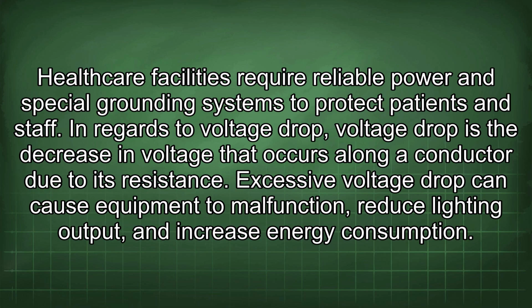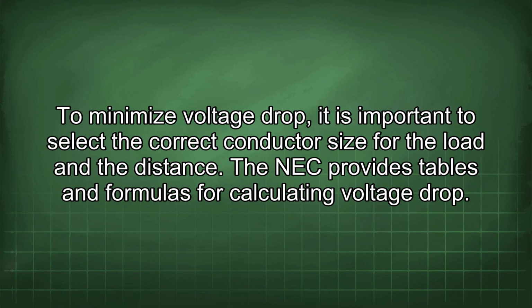In regards to voltage drop, it is the decrease in voltage that occurs along a conductor due to its resistance. Excessive voltage drop can cause equipment to malfunction, reduce lighting output, and increase energy consumption. To minimize voltage drop, it is important to select the correct conductor size for the load and the distance. The NEC provides tables and formulas for calculating voltage drop.